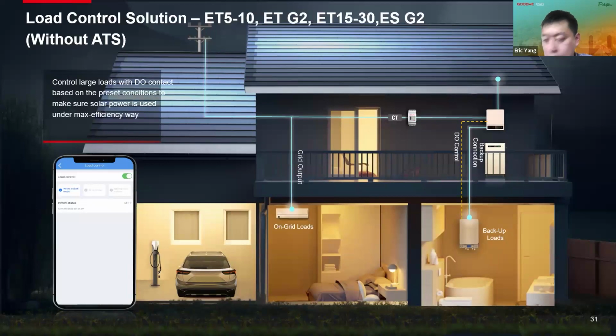And this is the load control solution for the ET 5 to 10, ETG2, ET 15 to 30, and also the ESG2 series, without ATS. That means if the customer wants to control some special loads such as a heat pump or an EV charger, we have this dry contact. This dry contact can communicate with the loads directly, such as the heat pump. It means the inverter can turn these special loads on or off separately. This load may be very big, such as the heat pump, and it is not an emergency load.